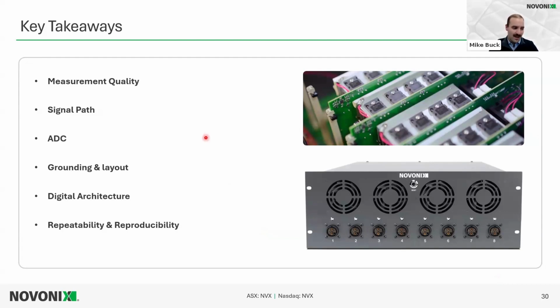The grounding and PCB layout are major factors in determining whether the accuracy of the readings in the instrument is good or bad. And there are usually many iterations in a design that it takes to get the grounding and the layouts perfect for the channel boards or the circuits that you're using in high precision equipment. Digital communication architecture can determine the scalability and the adaptability, and it's not to be minimized in its importance, because to get that clean data from the converter to the software, it's important that the design and the architecture of the digital is correct and scalable, and otherwise your data getting from the cell will not match what you expect it to match.